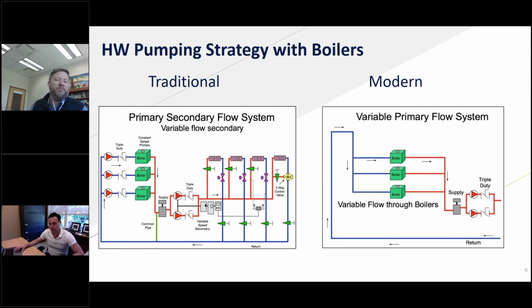You'd call that a limitation now from where we sit, but the thought process at the time was to create a boiler that would vary its capacity but wanted to see a constant flow. Because of that, we ended up with lots of systems out there. At the start, we had constant flow systems with 3-way valves on all of our terminal devices. Through time, we've tried to get more efficient. In an effort to get more efficient, we're putting 2-way valves on our terminal devices, which means we can now vary the flow for the system, but we can't yet vary the flow for our prime movers or our boilers.